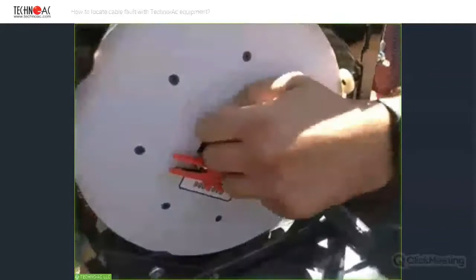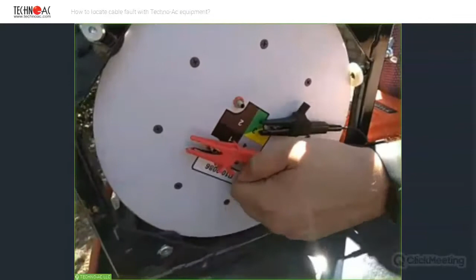I will switch the connection of the TDR to other conductors of the cable, and we will see what the device will tell us, like a fortune teller. Let's do it like this. Now we have switched the conductors of the cable, and you can see at the same distance, the graph is going down like this.